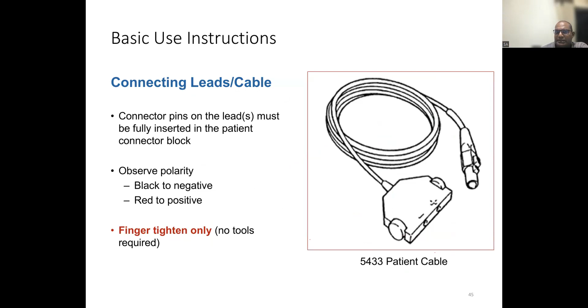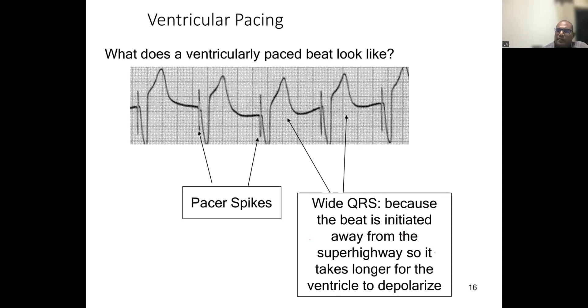Then the more important part is to understand what happens once you fix this device and adjust the parameters, and the patient is supposed to get a rhythm. If the patient doesn't have a significant rhythm, then you can adjust the parameters to achieve the rhythm that we want the patient to have. Either looking at the monitor, or more usefully, at an ECG rhythm strip or a 12-lead ECG, you will see certain things like spikes, and then a QRS complex, which is not necessarily similar to what you would see in a normal patient. Depending on how many pacing wires we are using, you might see more than one spike, but don't worry too much, because in emergency situations we only want to pace the ventricle. To maintain a cardiac output, pacing the ventricle is more than enough.